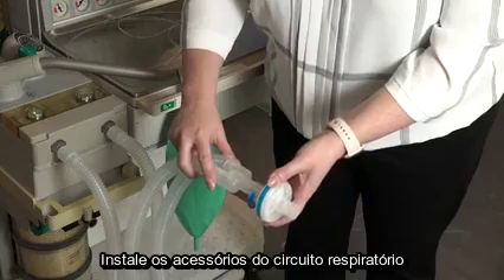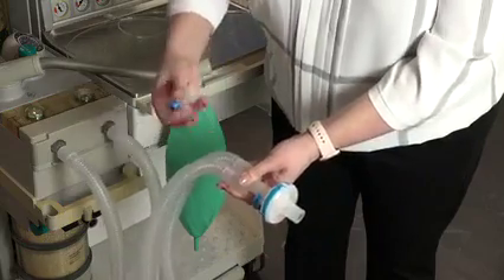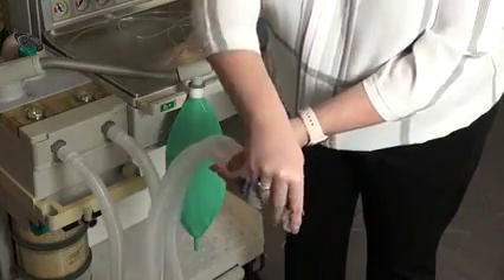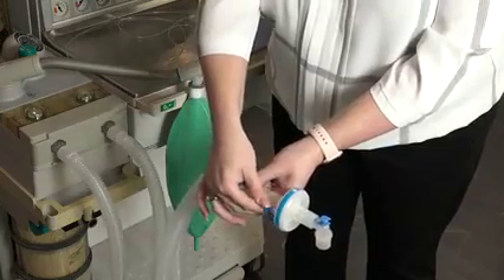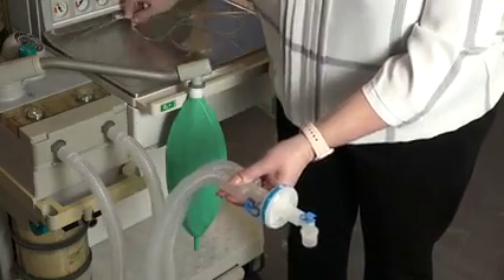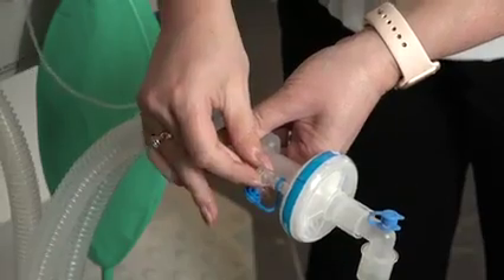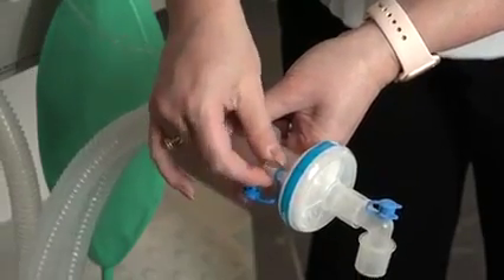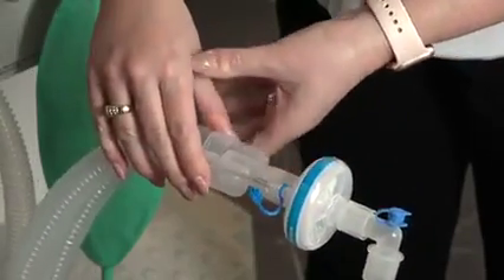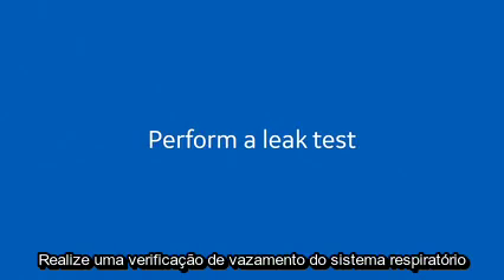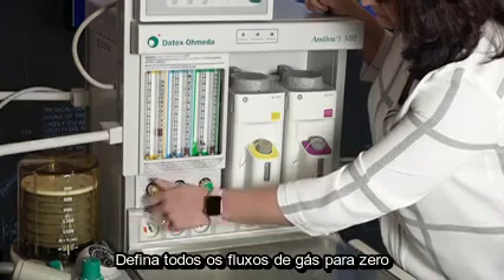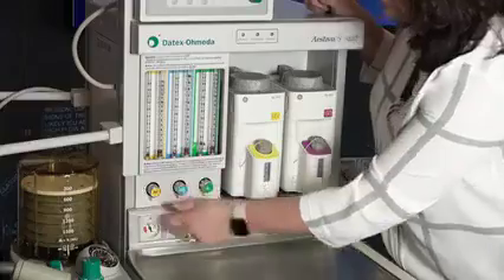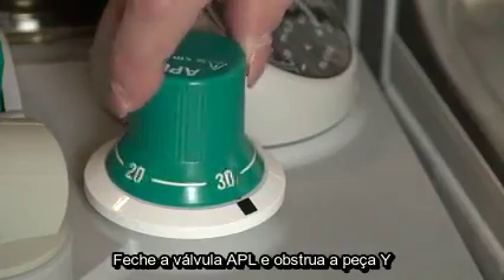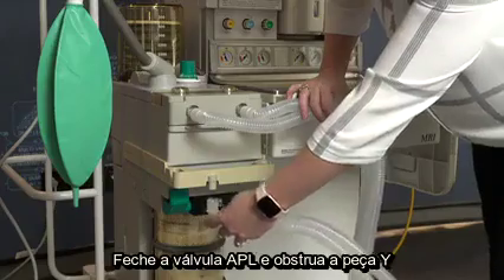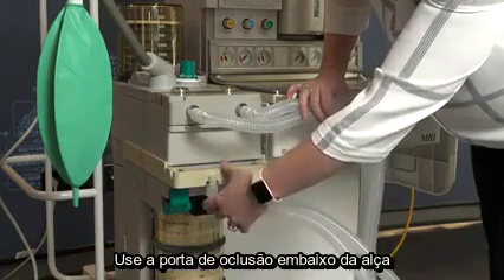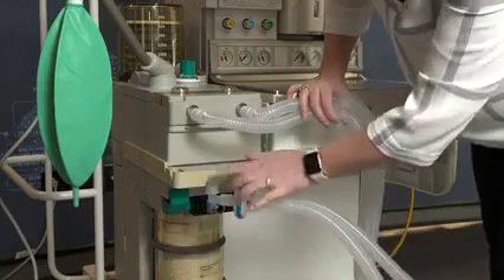Install breathing circuit accessories. Perform a leak check of the breathing system. Set all gas flows to 0. Close the APL valve and occlude the Y piece. Use the occluder port underneath the handle.